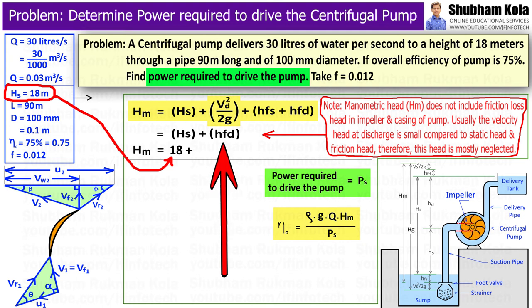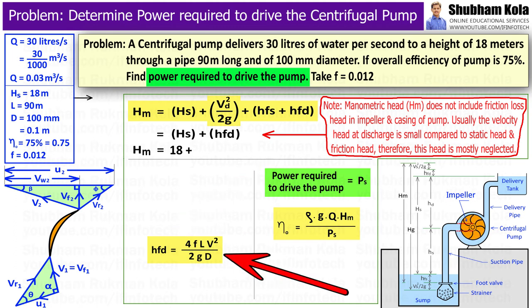And we need to calculate friction head loss. That is, hf we need to calculate. So, it can be calculated by the formula hf equal to 4fLV² upon 2gD, where friction factor small f equal to 0.012.